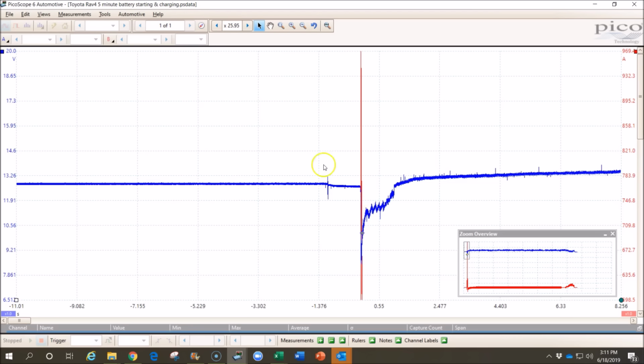You might recognize that when we do other battery load tests, such as using a carbon pile load tester or the min-max function on our multimeters, 9.6 is the minimum acceptable voltage. But because this lab scope is so much faster, it captures this thin little spike right here, so we have to lower that threshold, and 8.0 volts is the minimum voltage that's acceptable.